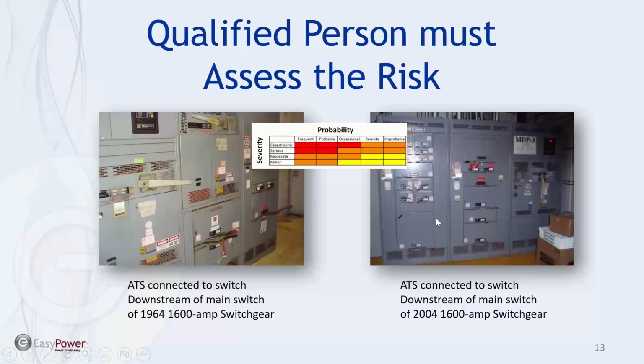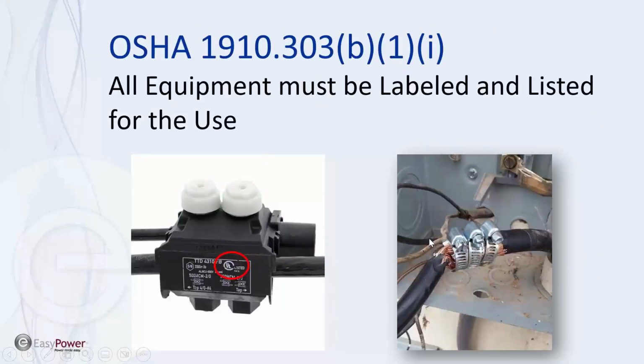So this is what risk assessment is all about, and this is taking a look at things from the standpoint of equipment. All equipment has to be labeled and listed for the use. So I showed you breakers and boxes and stuff. There are 3 ratings: load ratings, fault current ratings, and voltage ratings. It has to be labeled and listed. Boxes, breakers, splices, like this is a UL listed splice, tells you the size of the wire that can be used. This has a labeling and listing, but it's labeled and listed for a hose clamp.